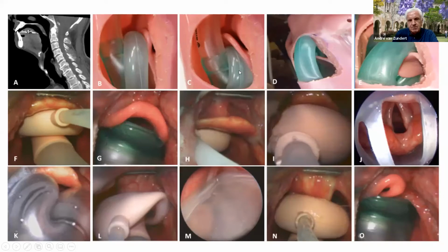It should not sit too deep. If it sits too deep, you see here, there's no alignment anymore. If it sits superficial, again, there's no alignment anymore. And the risk here is dislocation of the device. During maintenance of anesthesia, all of a sudden you can lose your airway because the device is now dislocated from its position. And another thing is that the epiglottis sits in the device itself, creating air leakage and sometimes even complete blockage as shown in here.